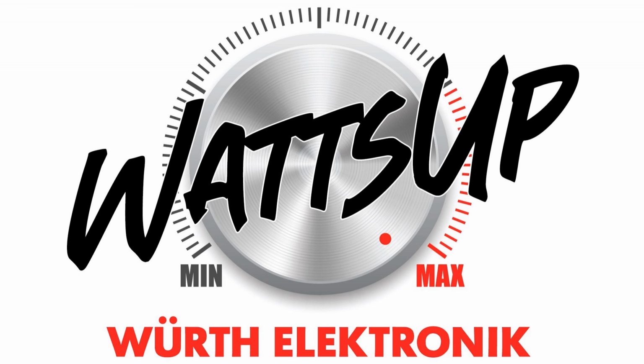Now looking into the copper losses, the copper loss is estimated using the I square R loss. So the RMS currents were already calculated previously. The copper loss gives us 381 milliwatts. So the total transformer loss is core plus copper loss, which gives 877 milliwatts. And the efficiency can be calculated as 1 minus the 877 milliwatts divided by the power, which gives us 94.85% theoretical transformer efficiency.